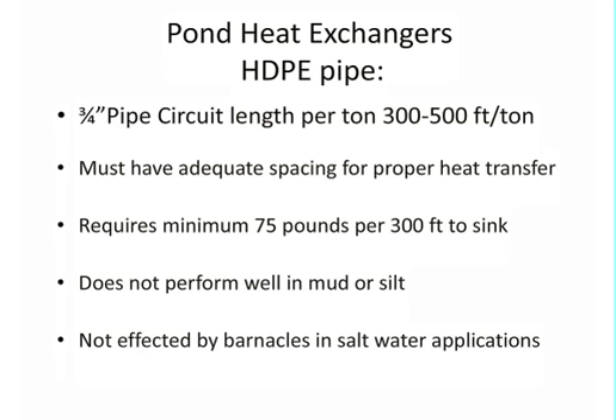Let's talk about the various types of heat exchangers. HDPE pipe, high-density polyethylene pipe, typically 3/4 inch, 300 to 500 foot length per ton, depending on the environment and your particular load conditions. You must have adequate spacing within those tubes for proper heat transfer - this is a crucial component.